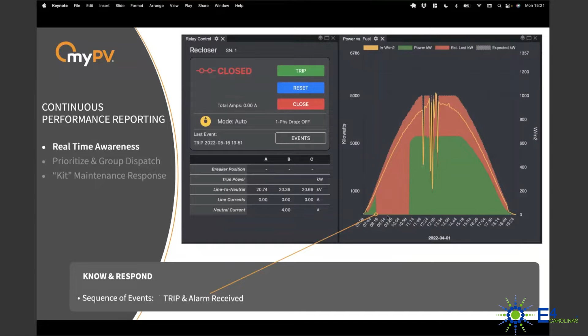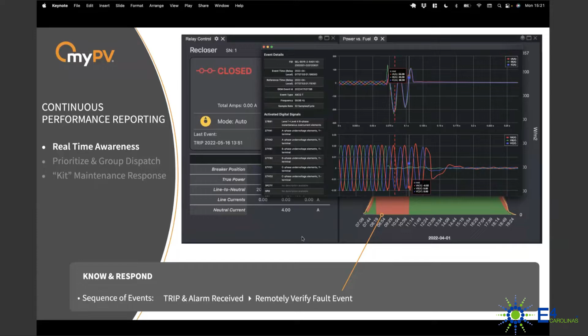So we had a trip, a fault of some type, and we received an alarm. Our operators were then able to remotely access the site through a secure interface, and they were able to actually verify that fault event, again without anybody having to go to the site. Over the course of the morning, we were in communication with the utility from our operations center in order to understand that there had been a utility side fault. And once that fault was cleared, we requested permission to close our facility back in. Once we received that permission, we were able to use this control tile right here to send a close command and verify that it had actually closed.